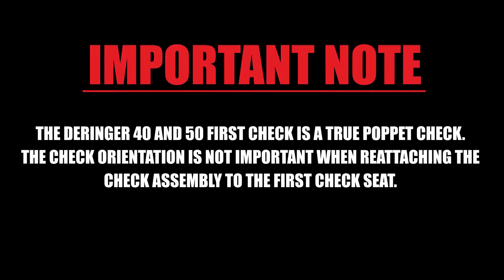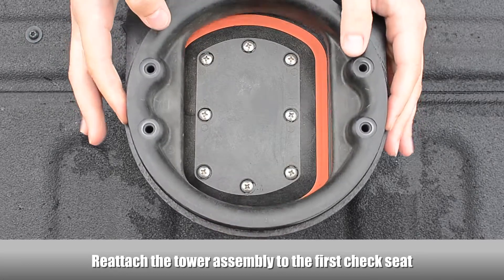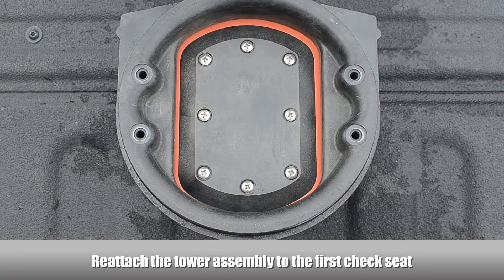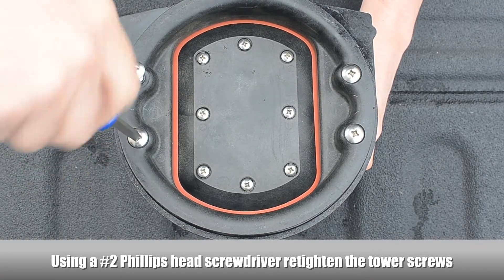The Deringer 40 and 50 first check is a true poppet check. The check orientation is not important when reattaching the check assembly to the first check seat. Reattach the tower assembly to the first check seat and, using a Phillips head screwdriver, re-tighten the tower screws.